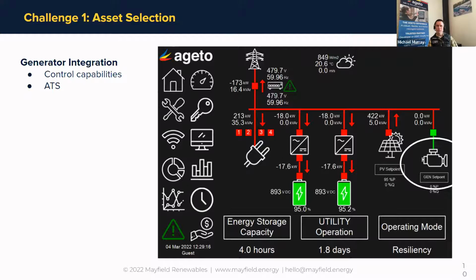Because if you don't do that, the ATS is kind of the limiting factor. On the Mayfield or the OMD project that we've been talking about, the ATS had to stay in there because it was part of the emergency system. So the way we had to integrate it is we rerouted the normal side of the ATS to the microgrid panel. And then when the batteries are low and there's no sun, we would open a load drop contactor, and that would black out the normal side. Then the ATS would go through its normal functioning to have the generator kick on, and it'll switch over to emergency operation mode. But every time that happens, there's a short power outage and it's not a seamless experience. Whereas if we could upgrade the generator, it would be a much more complete solution.